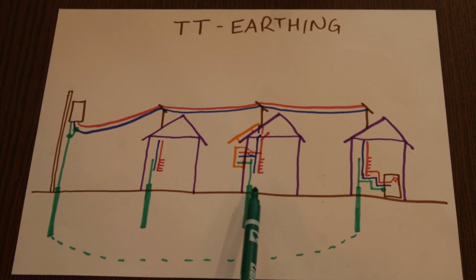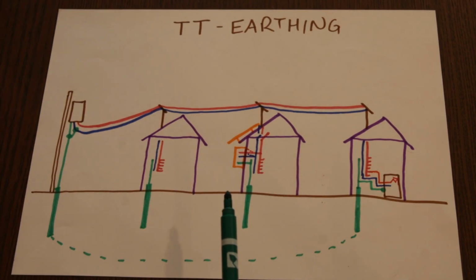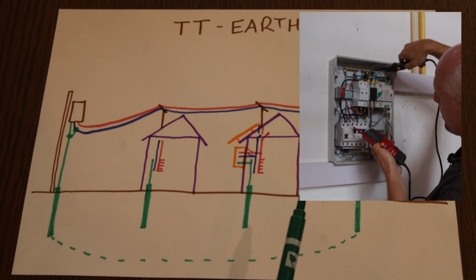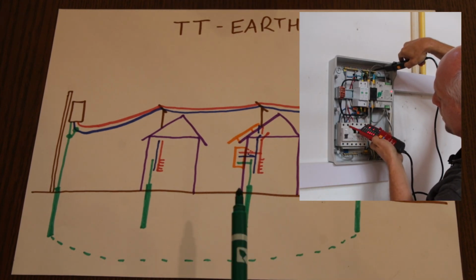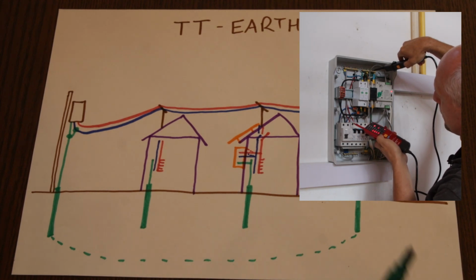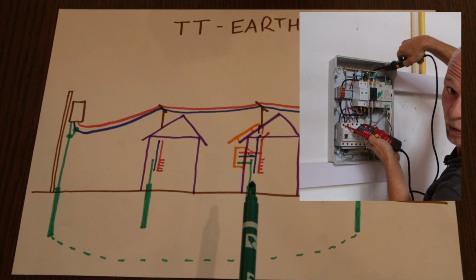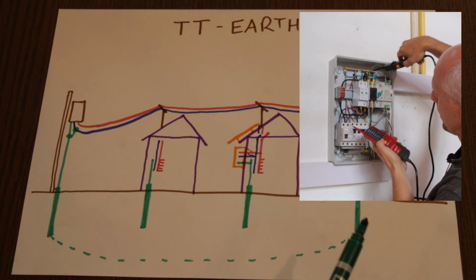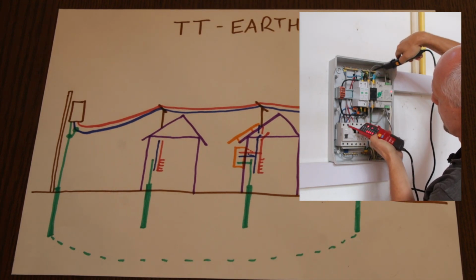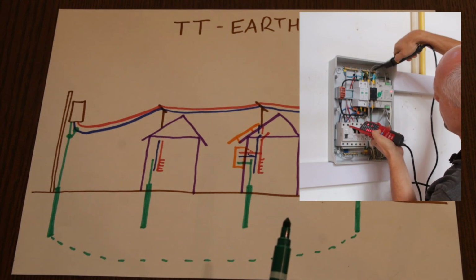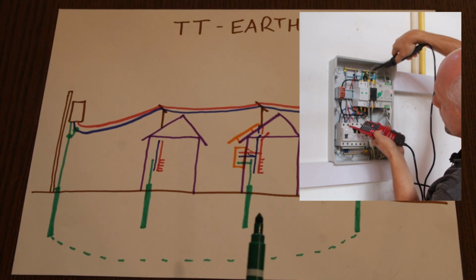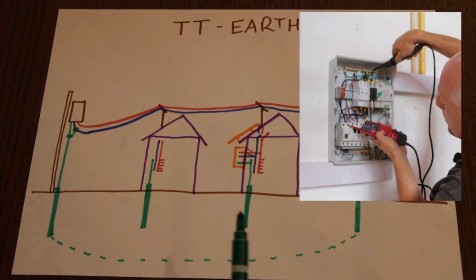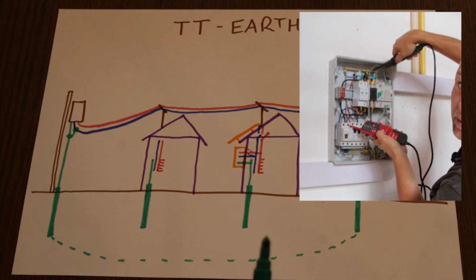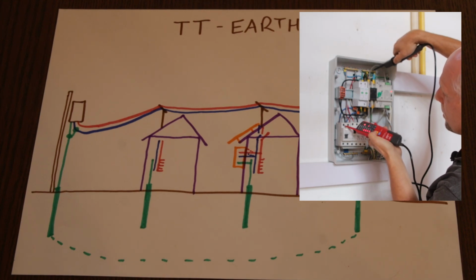Usually an inverter will be an isolated power source by nature. So if you do not define which leg is phase and which leg is neutral, by bonding that leg to the earth, it would just be floating around. So neutral and phase wires would be somewhere in between 0 and your maximum voltage. And this is something that does have advantages in certain situations, but not in house installations. There you always want to have defined which wire is neutral, which wire is phase.